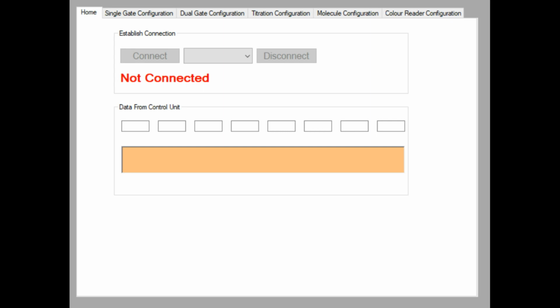It's also, under some conditions, much quicker to configure the unit using this computer control software that you're looking at here at the moment, rather than stepping through all of the hierarchy of menus on the control. But just to confirm, everything which the unit can do, it can do independent of the computer. So calibration data is stored on the module, but it can also be transferred to the computer. It can be transferred back from the computer to the control unit. So it can work in either direction.